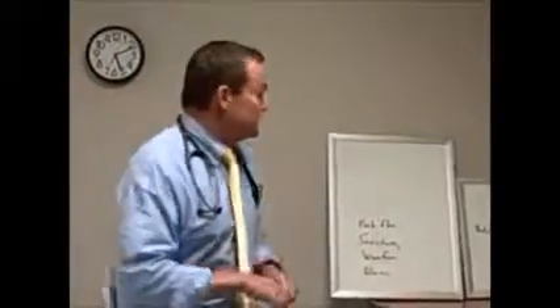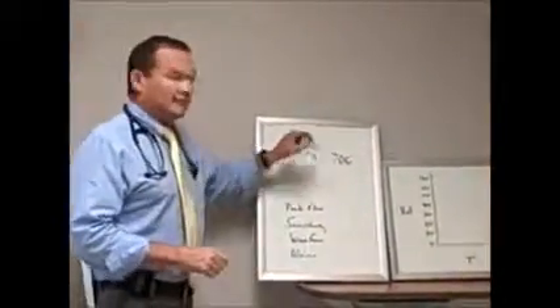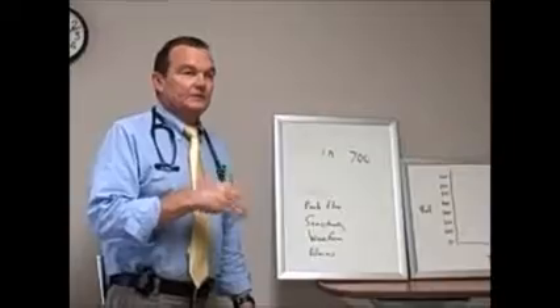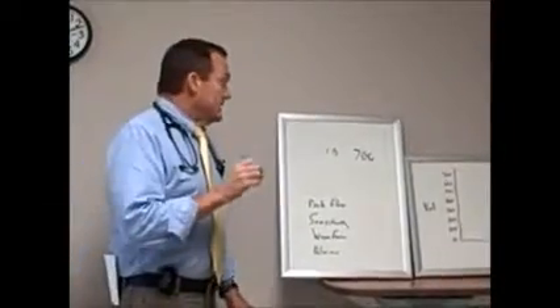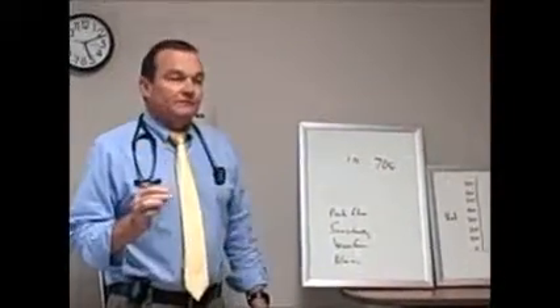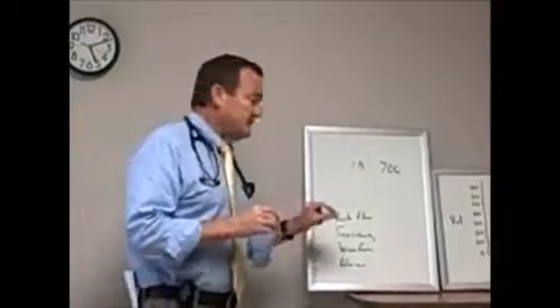Peak flow. You know what peak flow is? Peak flow is what they set the flow on the ventilator. So if you put someone on an IMV of 10 and a tidal volume of 700, the peak flow is what that tidal volume is delivered at in liters per minute, okay? If you don't designate a peak flow, respiratory sets the peak flow. Well, that's the other thing. I knew I was leaving off something.